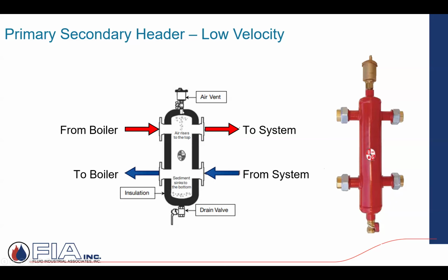And then the other function that some of the guys in the industry will take advantage of is if I'm in a mechanical room where maybe it's not a brand new building, but it's a retrofit, it's a renovation. So I have existing piping and radiation out of the building, but I've cleaned up the mechanical room. I might have some sediment coming back from the system. What I can do is use this device, again because of the low velocity, as a dirt separator. So I can be my primary secondary connections, I can be my air elimination, and it can be my dirt separator. And then what happens is they'll add this drain, this valve at the bottom, and use it as a blow off. So they'll blow off any of that sediment that might collect at the bottom of that low loss header or that primary secondary header.